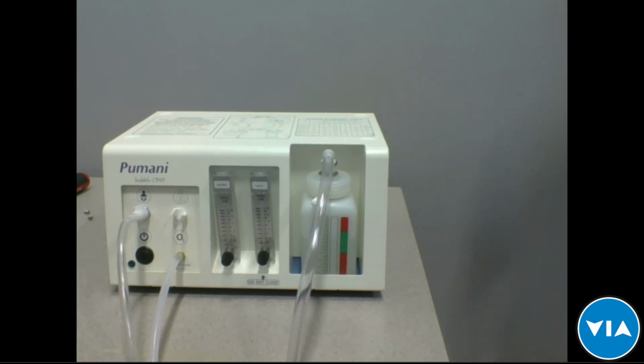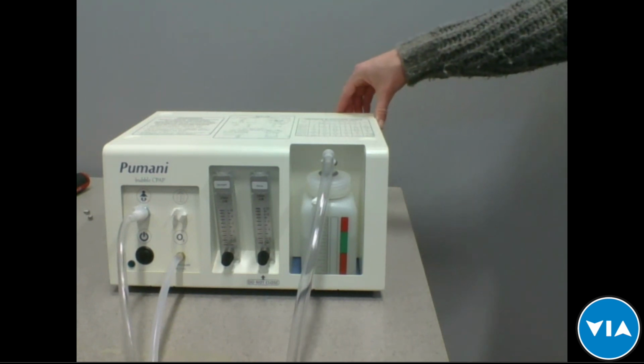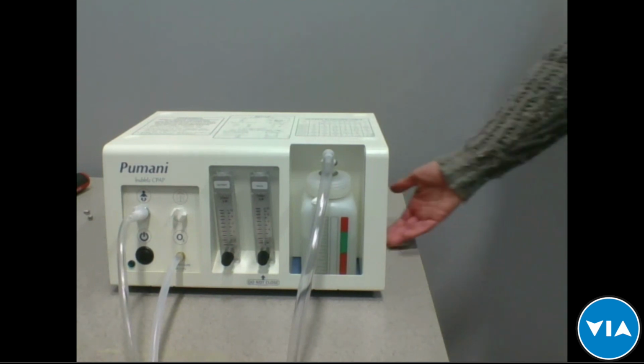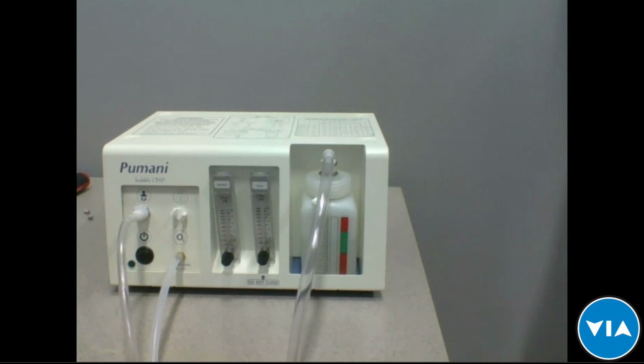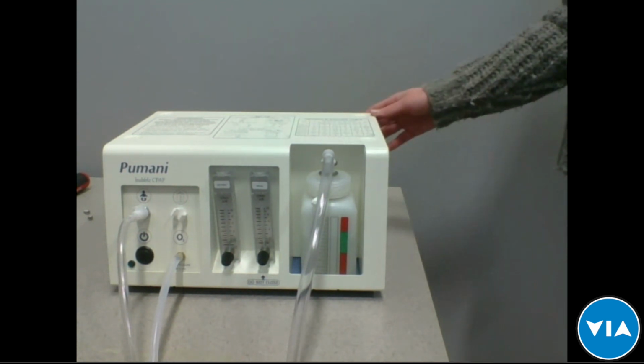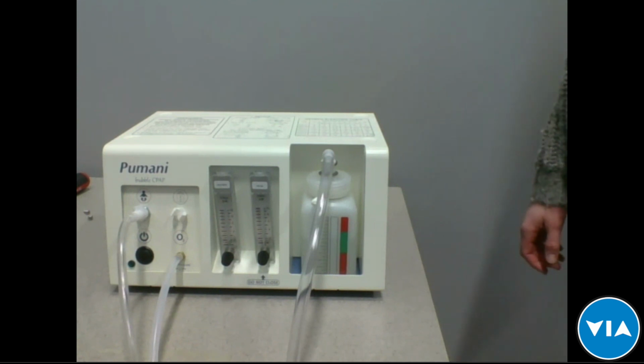The other part that needs to be changed or at least checked is the filter inside the pump. So that filter, when the Pumani pulls in air from your setting and pulls it through a filter, and then it goes into the pump and then to the patient. And that filter just gets out big dust particles to protect the pump. Well, also depending on where you're using it. If you're using it in a higher level NICU that has climate control and closed windows, it will take a lot longer for the pump filter to get dirty. But if you're using it in a hospital that's sort of open air hospital that has more dust, the pump filter will get dirty quite quickly. And so we recommend that you check that pump filter every 6 months and replace it every year.